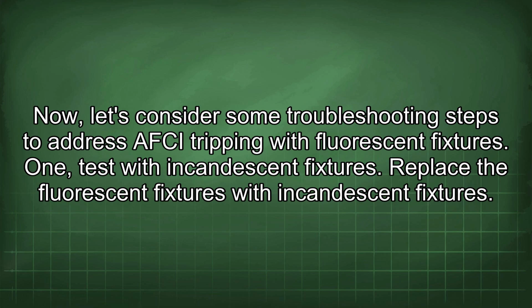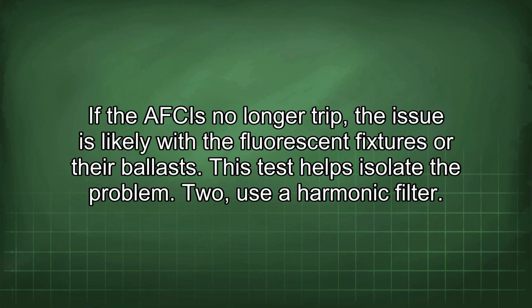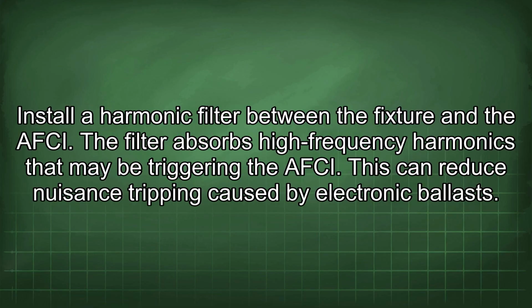1. Test with incandescent fixtures. Replace the fluorescent fixtures with incandescent fixtures. If the AFCIs no longer trip, the issue is likely with the fluorescent fixtures or their ballasts. This test helps isolate the problem. 2. Use a harmonic filter. Install a harmonic filter between the fixture and the AFCI. The filter absorbs high-frequency harmonics that may be triggering the AFCI. This can reduce nuisance tripping caused by electronic ballasts.